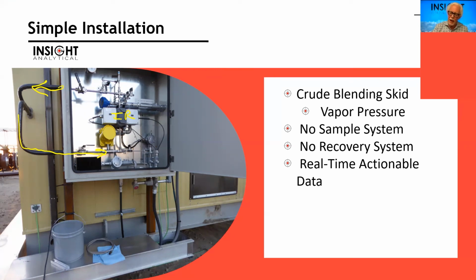And so, yeah, when you look in this panel, we put isolation valves on the inlet and the outlet side. Pressure and temperatures, there's a lab grab sample point in there. Why is it throttled? Good question. Greg, smart guy. Probably shouldn't be. I'm not sure why they didn't have that valve wide open when they took this picture.